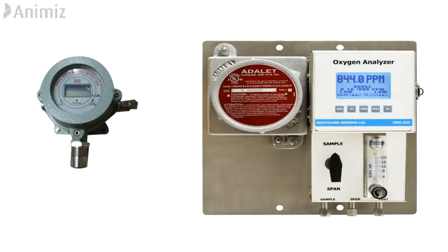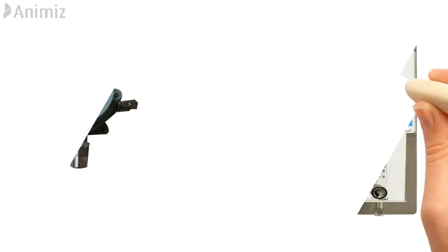Oxygen analyzer to be provided in vent line of hydrogenator and addition of hydrogen to be interlocked with LOC greater than 3%. Hydrogenator facility to be designed in such a way that drain material from hydrogenator not to be mixed with main drainage system. Wastewater from hydrogenation facility to be stored separately away from direct sunlight. Wastewater from hydrogenation facility to be treated and ensure its pH is neutral.